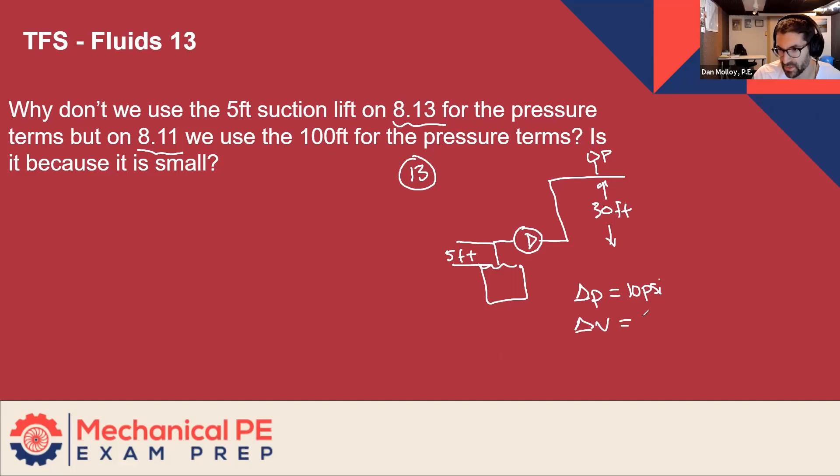We're neglecting velocity in this one, and then the Delta Z is the total difference. So it's the sum of the static suction lift of five feet and the discharge head of 30 feet. So it ends up being 30 plus five, which is 35 feet.